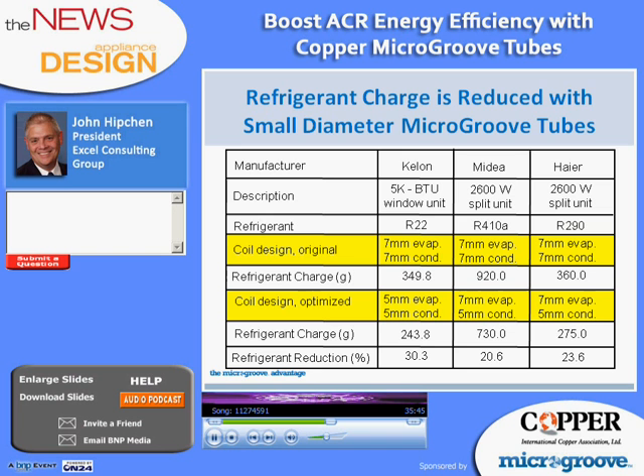When we compare original to optimized designs, we see that the window unit goes from 7mm to 5mm tubes for both the evaporator and the condenser, while the split type systems, both of them, reduce from 7mm to 5mm tubes for the condenser coils only. And, as you might expect, it is the window unit that reports the largest percentage reduction of refrigerant charge. But even the smallest refrigerant charge reduction, shown here of 20%, that's still quite sizable, and I'm sure welcome news to the accountant that's watching the bottom line.